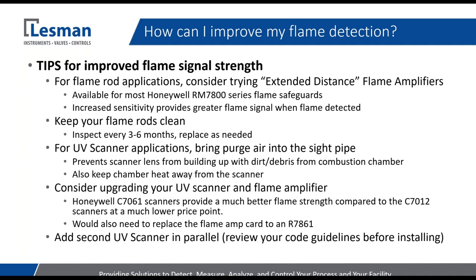For UV scanner applications, if you're not already bringing purge air into the sight pipe, it's a common and highly recommended practice. It keeps the scanner lens clean and free of debris. If you've got dirt or debris in the application, depending on where the sight pipe is, it could be collecting on the scanner lens. Bringing a little bit of purge air into the system will help keep that area free and clear so the dirt goes elsewhere downstream in the combustion chamber. It's also good for higher temperature applications where you could be getting heat transfer from the chamber acting back on the scanner — keeping positive pressure in the sight pipe will keep that scanner lens cool and prevent heat transfer from acting back on the UV scanner and its electronics.